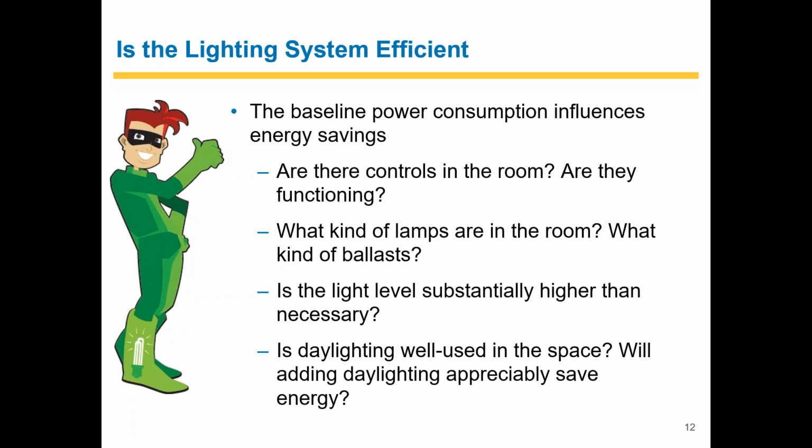I've done quite a few technology studies with some of the utilities out here in California where we look at existing lighting controls and try and assess whether they're actually still working 5, 10, 15, 20 years after they were installed. And more often than not, they're not working as intended.